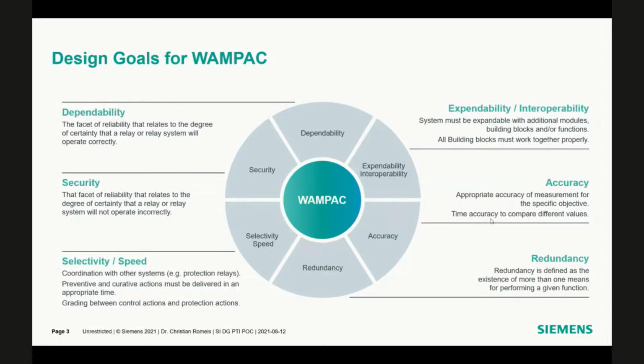And also the accuracy is very important. So here you have to decide if you want to use maybe M class in the PMU or P class, based on what your objective is. So for protection, maybe you use the P class, you need a fast acting system. And for metering or also model tuning, maybe you use the P and the M class plus very precise instrument transformers to get a very accurate result.